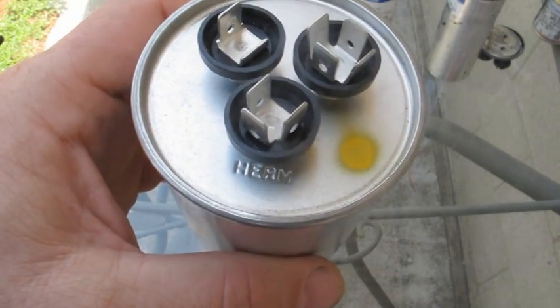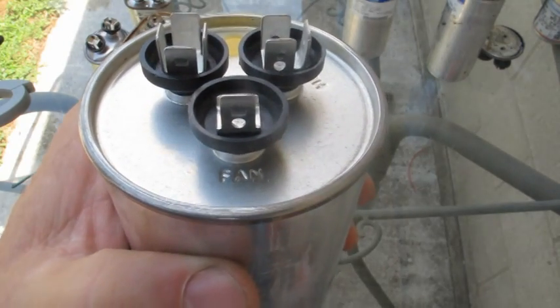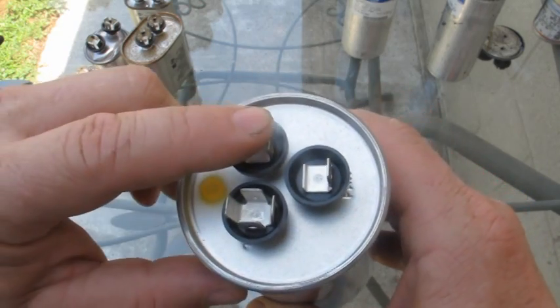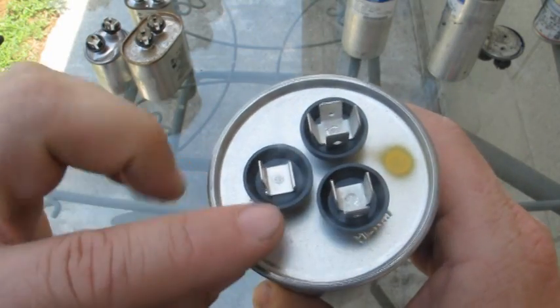You're going to have terminals marked HERM, one marked COMMON, one marked FAN. When you're testing them, you're going to go between common and compressor, and between common and fan. So these two should be 5, and these two should be 60.